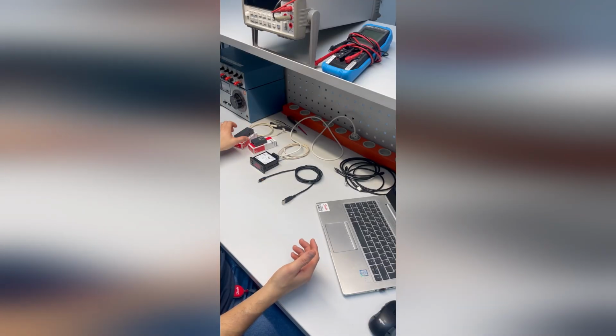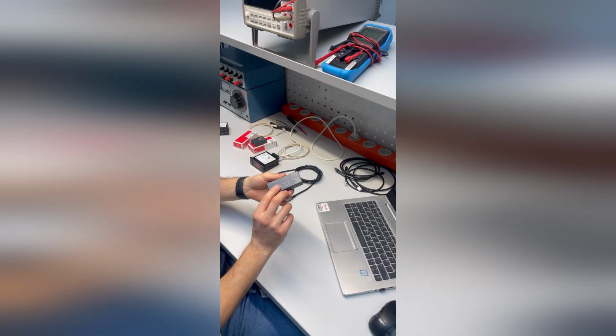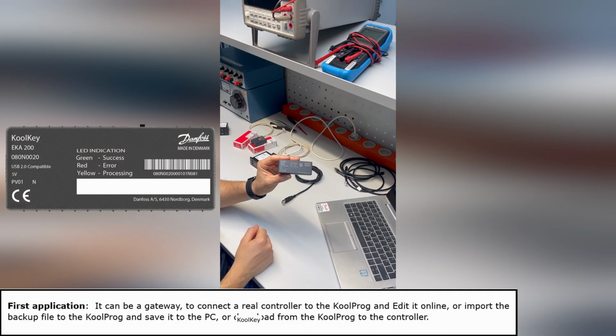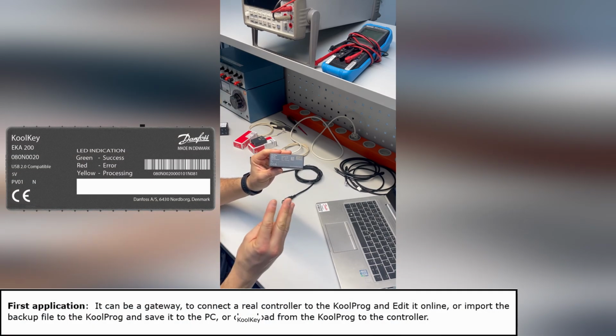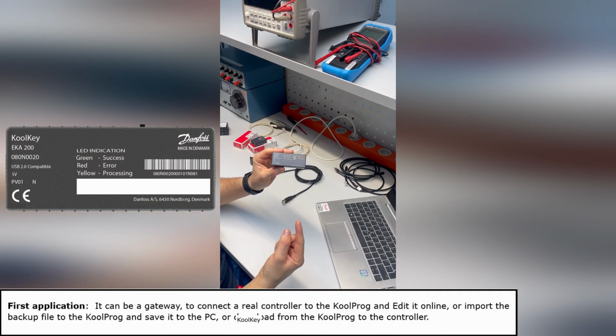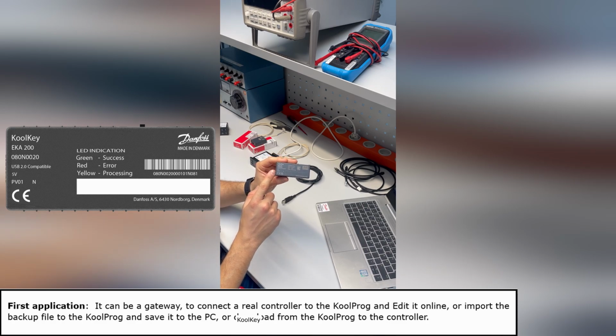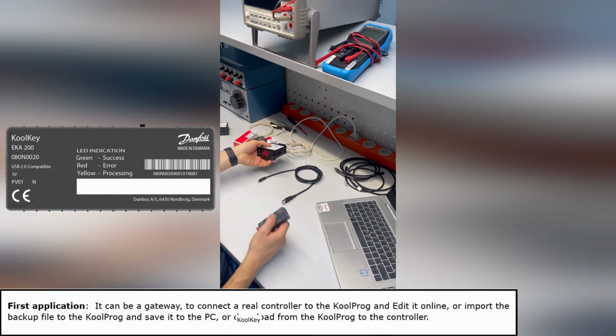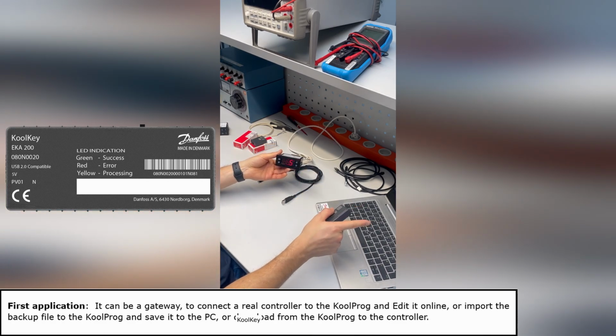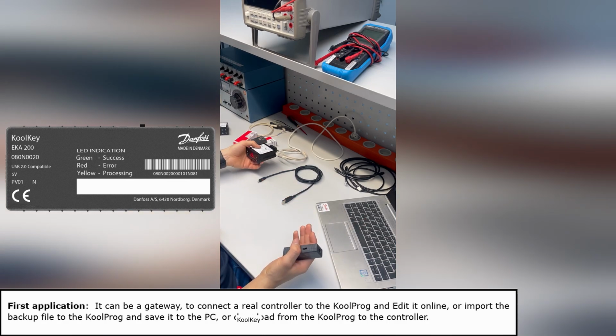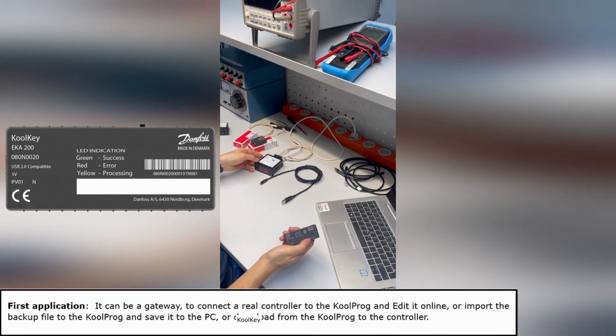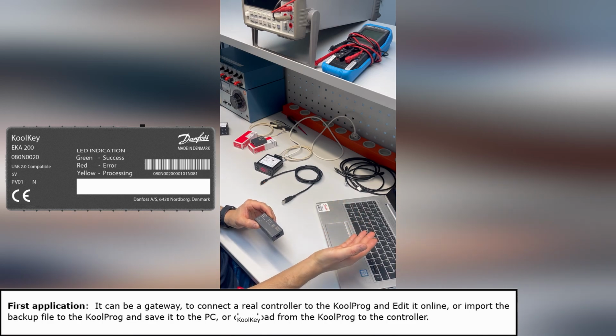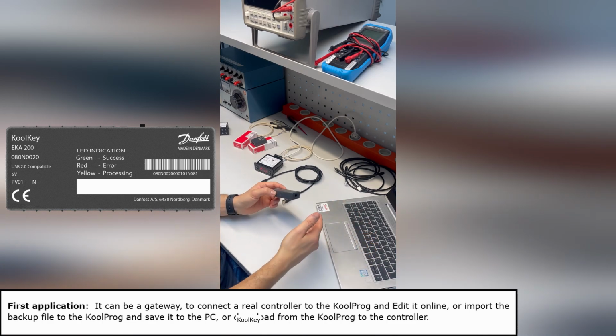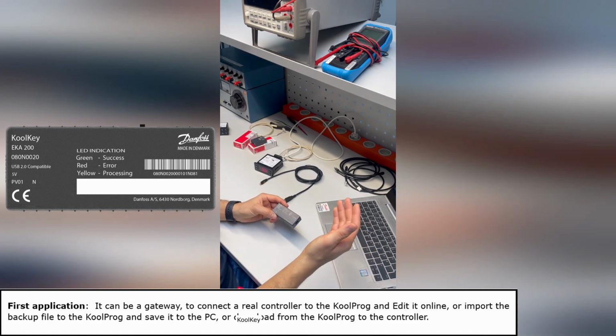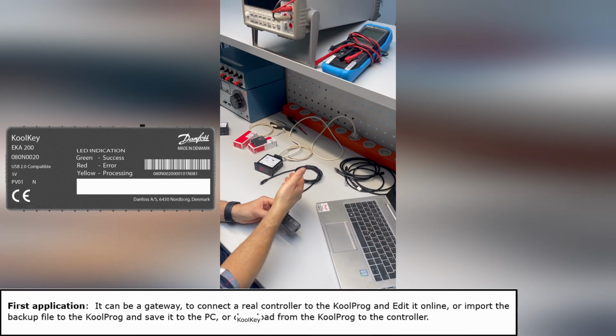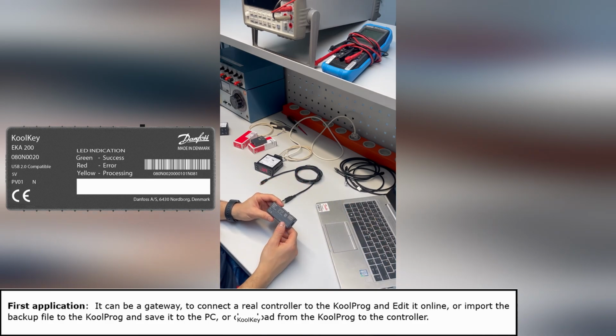Okay, and now let's talk about the KoolKey. So here we have our KoolKey. The KoolKey has three main applications. So the first application is that it can be a gateway to connect a real controller to the Koolprog in your PC and edit it online. Or you can also import the backup file to the Koolprog and save it to your PC to edit later, for example. Or you can also download from the Koolprog to the controller if you already have an application.